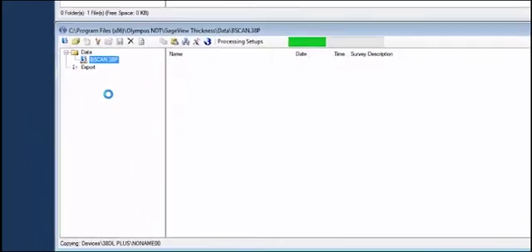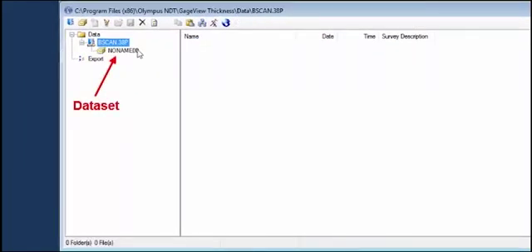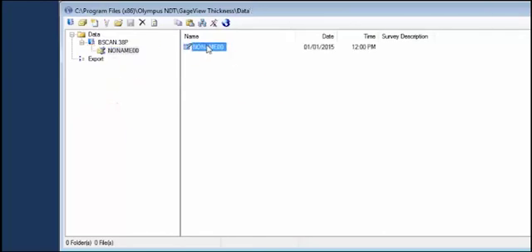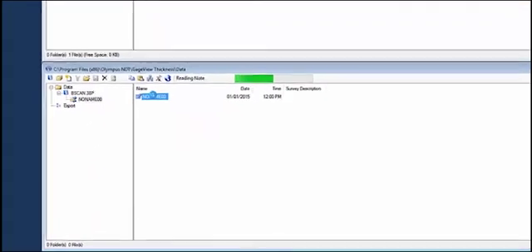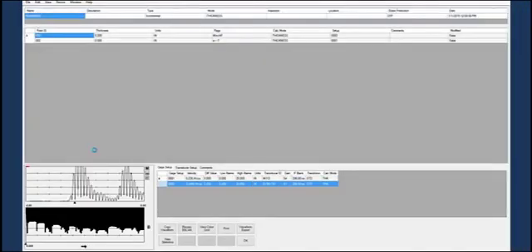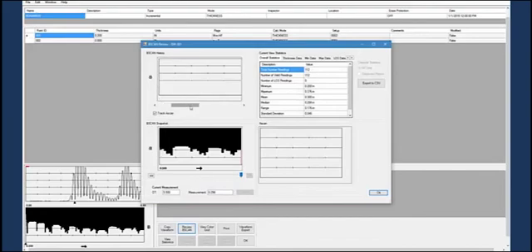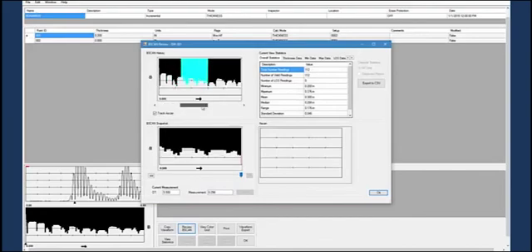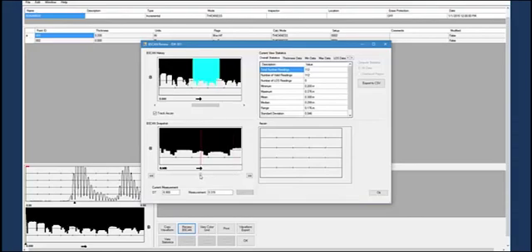Once the file is transferred, you can click the data set once and then double-click the survey file, which is the file name with the pencil and paper icon next to it. You can then click Review B-Scan. The image on top shows the full encoded B-Scan and allows you to highlight a certain portion of the scan to examine, while the image below displays the highlighted portion of the scan and allows the user to review the scan with the cursor.